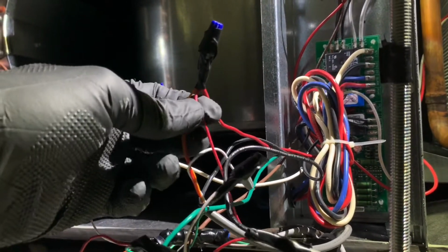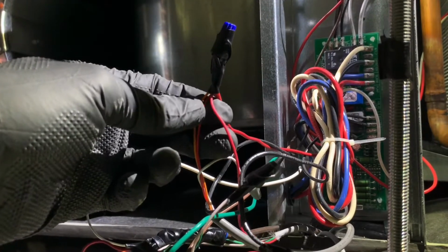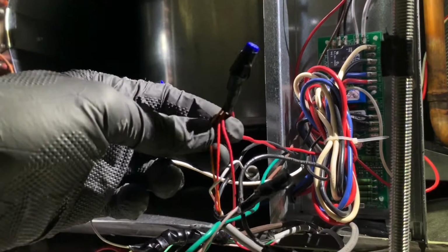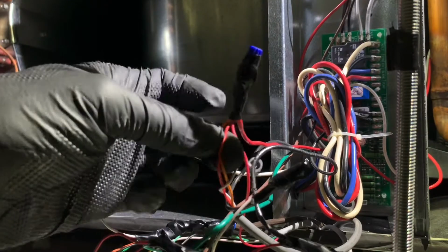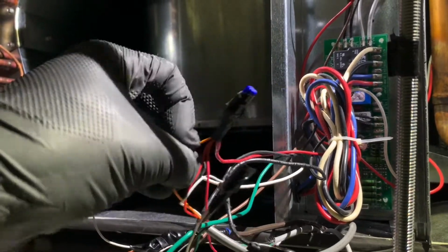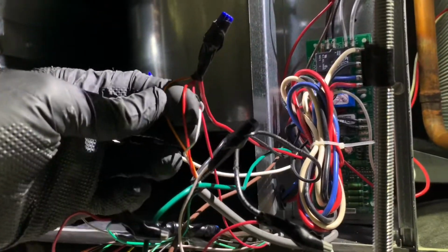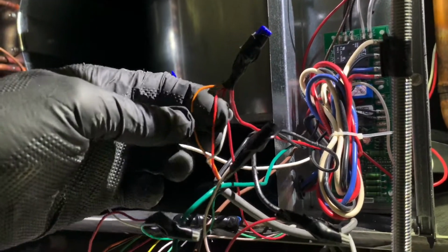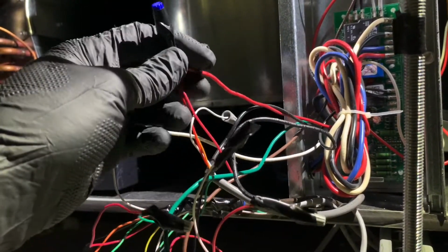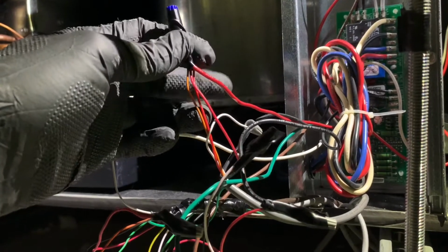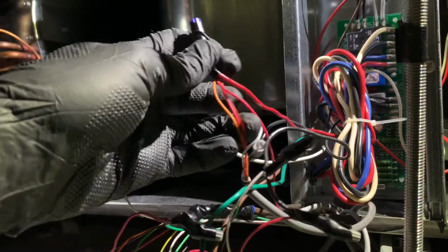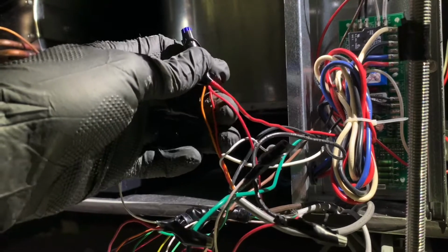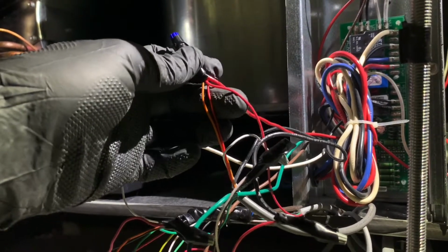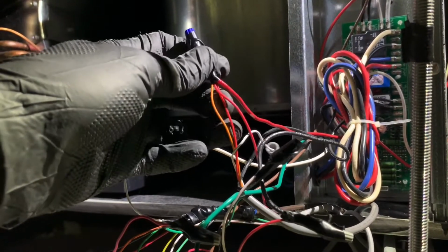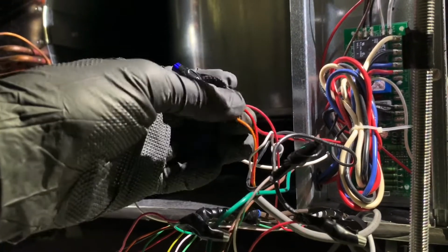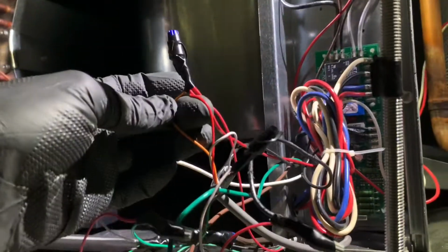And then we also have 24 volts going to the outdoor condenser, right? 24 volts hot. And then the other 24 volts right here, this one right here, is going 24 volts into the flood detector. And that's it for your 24 volts. Okay, so this one goes back to the air handler. This one to my outdoor unit or condenser unit, and this one right here, the skinny one right here, goes into my flood detector.